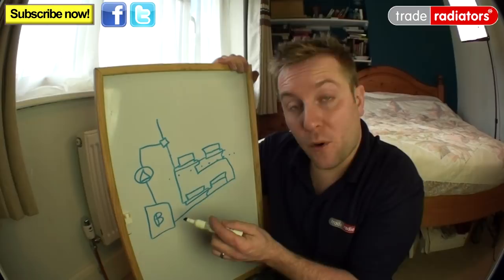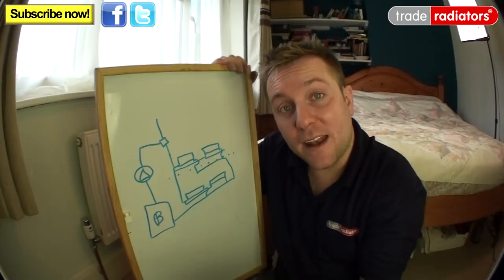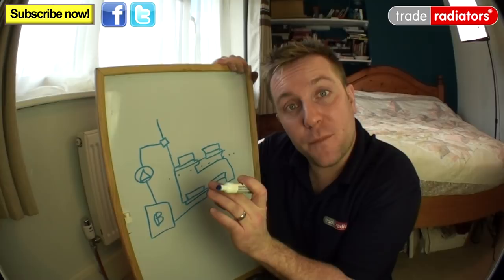So what we do is we go to what's called the lock shield end of the radiator, shut that all the way down, and then give it a quarter or half a turn back open again.